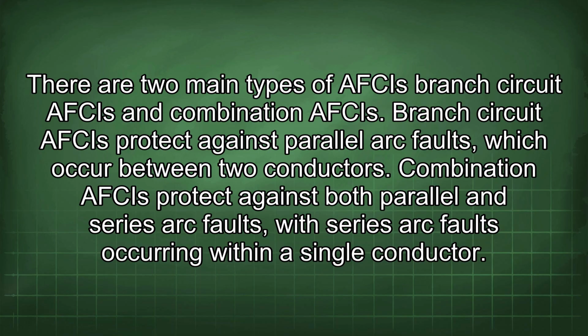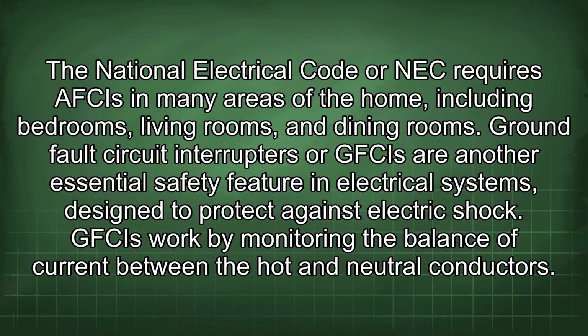There are two main types of AFCIs: branch circuit AFCIs and combination AFCIs. Branch circuit AFCIs protect against parallel arc faults, which occur between two conductors. Combination AFCIs protect against both parallel and series arc faults, with series arc faults occurring within a single conductor. The National Electrical Code, or NEC, requires AFCIs in many areas of the home, including bedrooms, living rooms, and dining rooms.